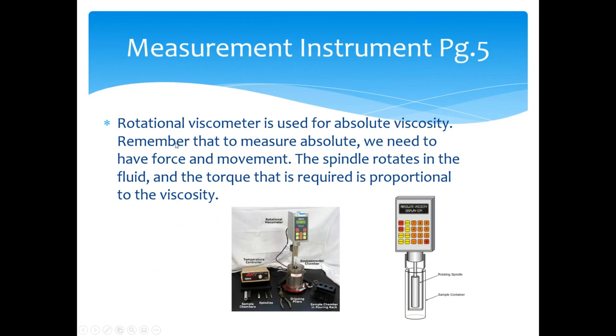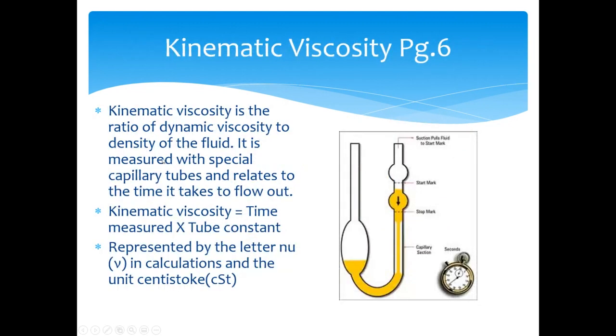Kinematic viscosity is the ratio of dynamic viscosity to the density of the fluid. It's measured with special capillary tubes — Ostwald tubes — and relates to the time it takes for the fluid to flow out. We fill a particular volume chamber with the fluid, allow it to drain through a restriction, and measure the time. That time multiplied by the tube constant gives us the kinematic viscosity measurement. Kinematic viscosity is represented by the symbol nu (ν), and its units are the stoke or centistoke.